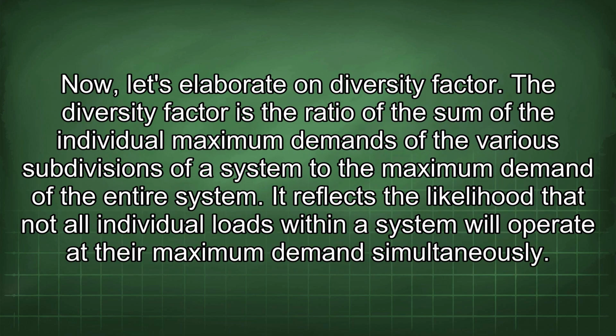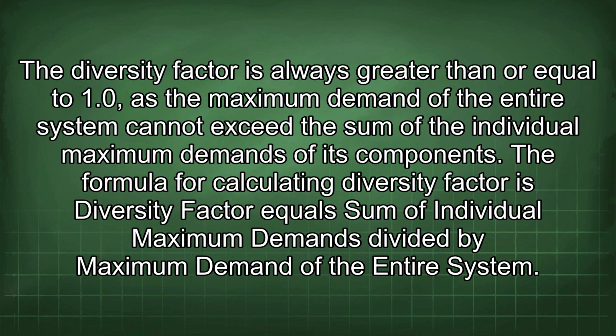Now let's elaborate on diversity factor. The diversity factor is the ratio of the sum of the individual maximum demands of the various subdivisions of a system to the maximum demand of the entire system. It reflects the likelihood that not all individual loads within a system will operate at their maximum demand simultaneously. The diversity factor is always greater than or equal to 1.0, as the maximum demand of the entire system cannot exceed the sum of the individual maximum demands of its components.